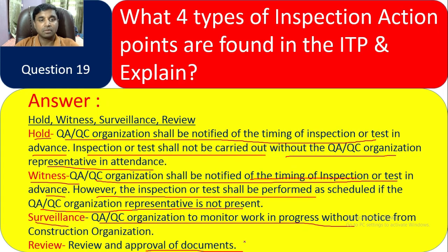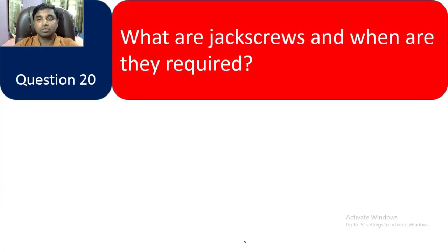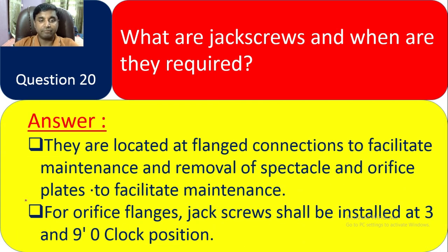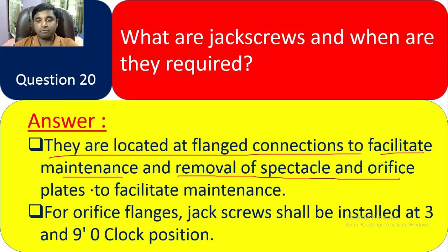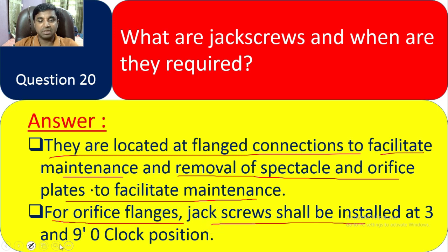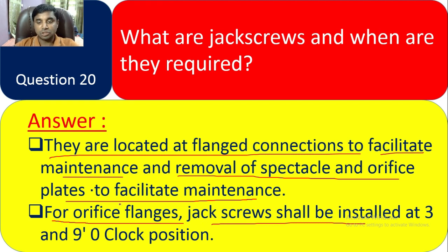Question 20: What are jackscrews and when are they required? Jackscrews are located at flange connections to facilitate maintenance and removal of spectacle and orifice plates. Jackscrews shall be installed at the 3 o'clock and 9 o'clock positions on orifice flanges.